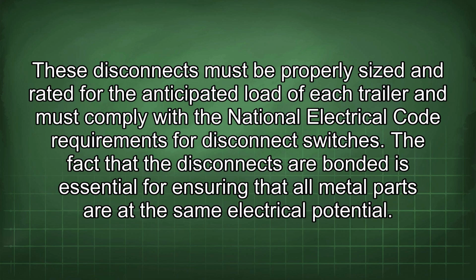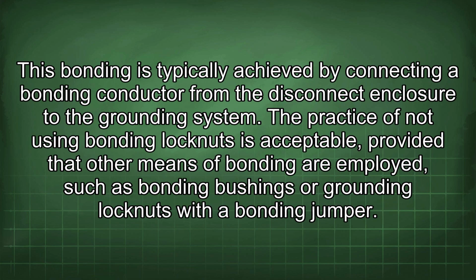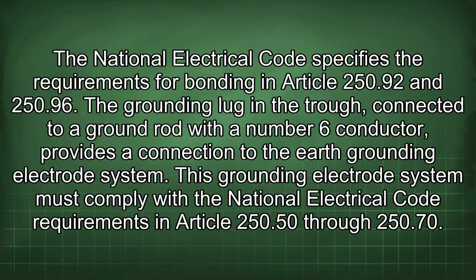The fact that the disconnects are bonded is essential for ensuring that all metal parts are at the same electrical potential. This bonding is typically achieved by connecting a bonding conductor from the disconnect enclosure to the grounding system. The practice of not using bonding lock nuts is acceptable, provided that other means of bonding are employed, such as bonding bushings or grounding lock nuts with a bonding jumper. The National Electrical Code specifies the requirements for bonding in Article 250.92 and 250.96.